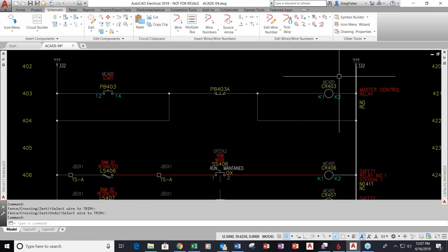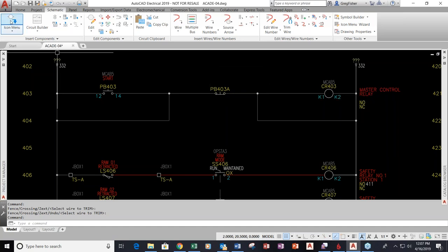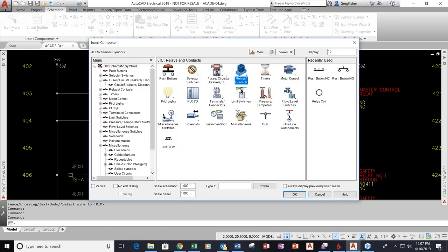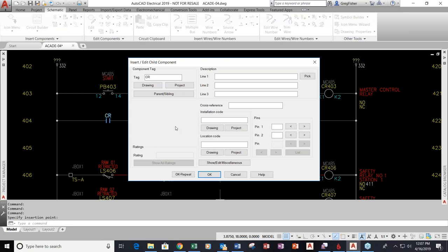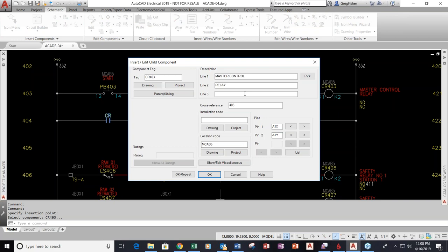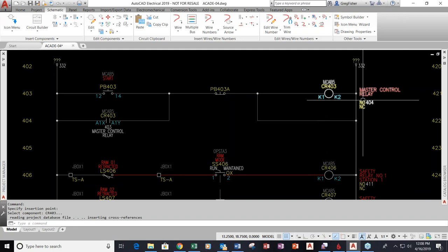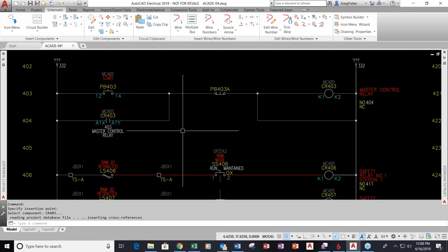Now I'm going to insert a child symbol. This is the parent symbol I dropped in, so I want to insert a normally open contact that gets tied back to this relay coil. This dialog box looks a little different because it's a child symbol — the tag does not come in automatically because I have to tell it who it belongs to. I'll pick it and, as you can see, it carries over all the same information placed on the parent and tells me the cross-reference of where the parent is. The parent symbol updated automatically — that's not going to happen in regular AutoCAD — and the child symbol updated so they know where each other are.